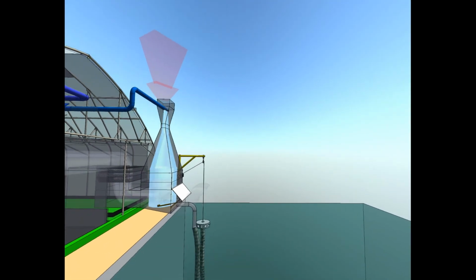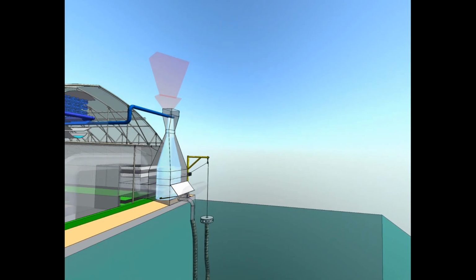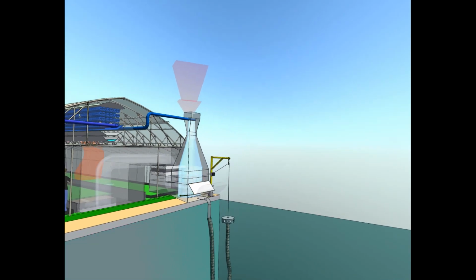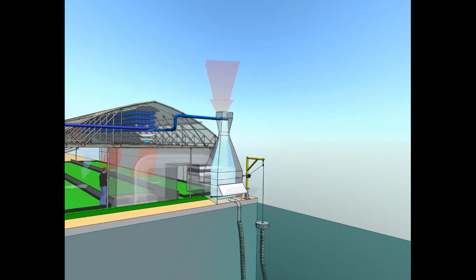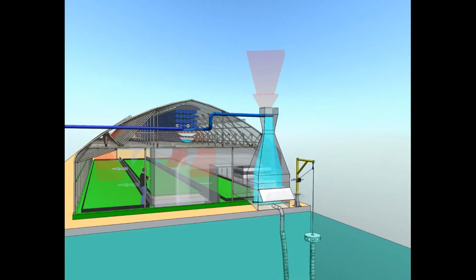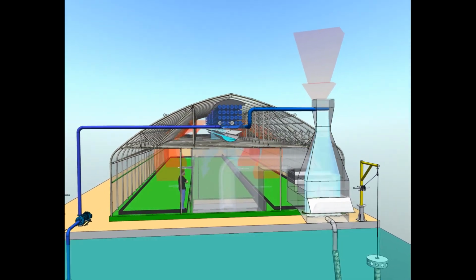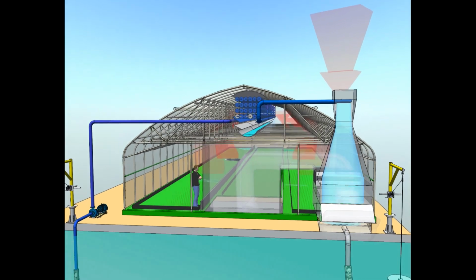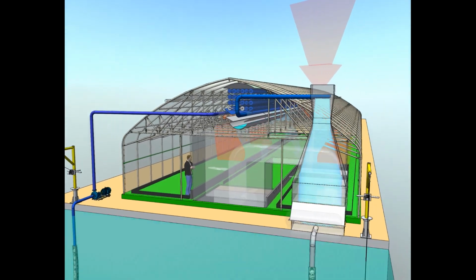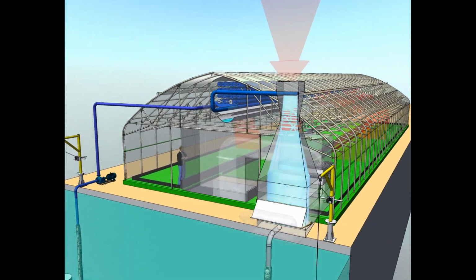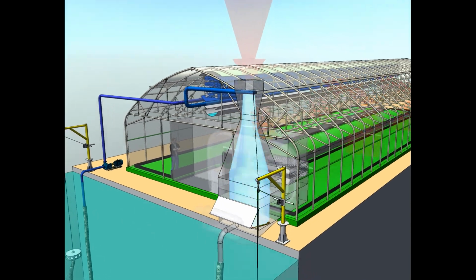At the exit from the condenser heat exchanger, the heated water is supplied to the Venturi scrubber, where it is sprayed into a restriction device, entraining hot atmospheric air with low humidity. At the same time, the air is humidified and cooled, and due to evaporation, the circulating water is also cooled and sent back to the pool, but with a slightly increased salt content.